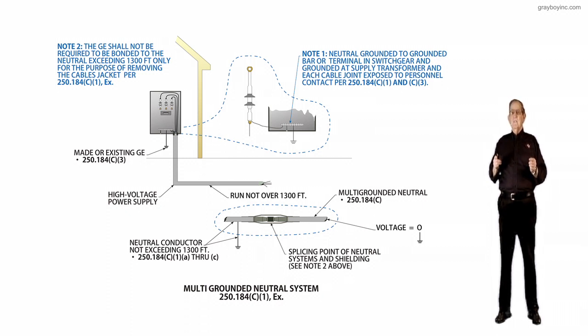The reason is that removing the jacket only to create a point for bonding creates a less desirable condition than allowing the further spacing between bonds. Removing the jacket creates a weak spot in the cable that could lead to premature cable failure. And bonding is also bonding to the shielding material, potentially affecting the shielding of the cables, that could also allow for undesirable EMF to flow at the point where this could occur.